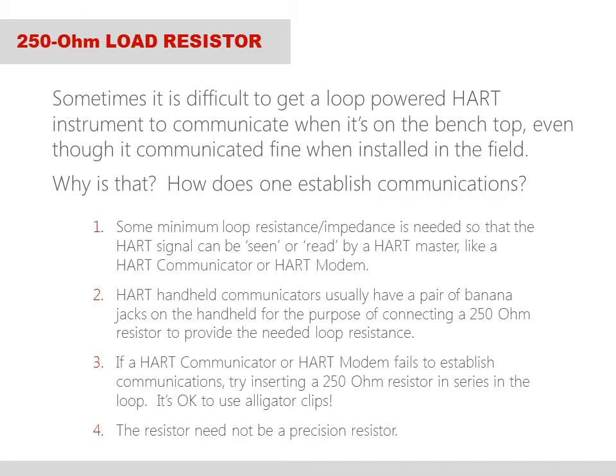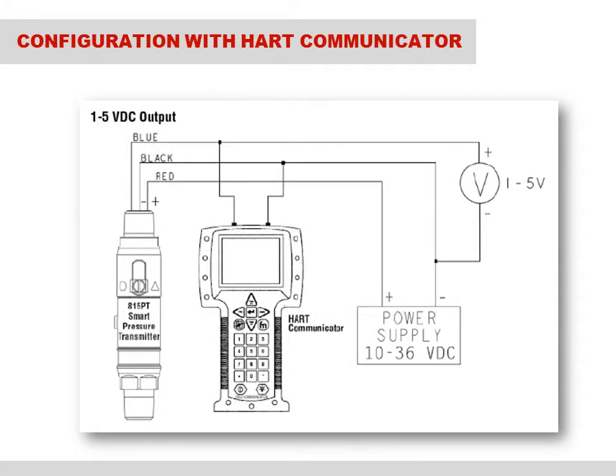In a real-world application, that is to say, in a plant environment, the significantly longer length of the plant's current loop provides adequate resistance. On a previous slide, we looked at how to connect the HART handheld communicator, or HHC, to the 815 PT to configure the unit for a 4 to 20 milliamp output. Let's look at how the HHC is connected to the 815 to configure the unit for a 1 to 5 volt DC low power output.